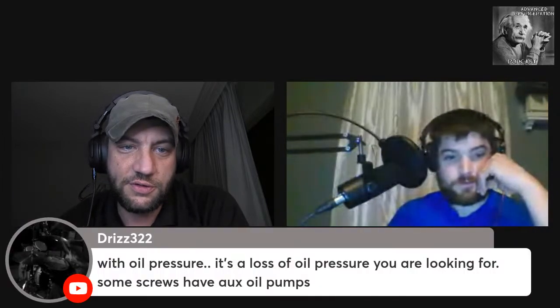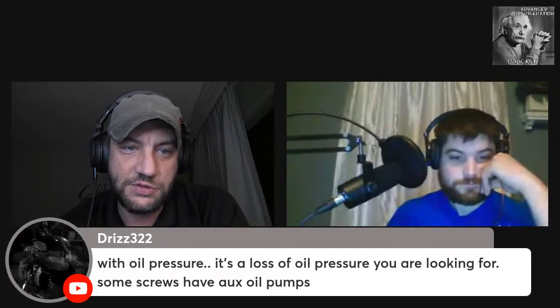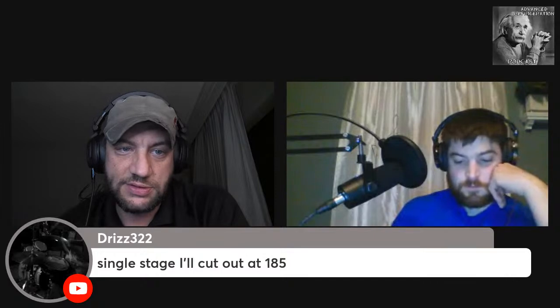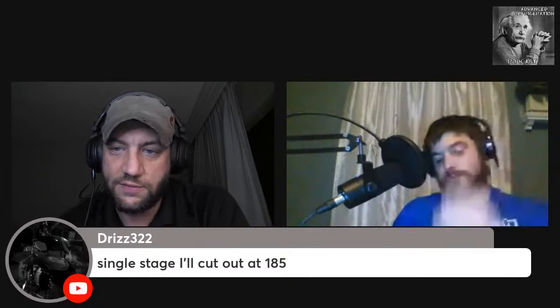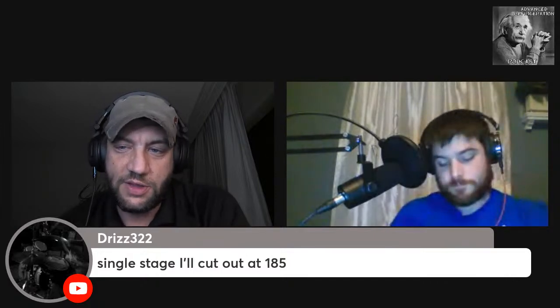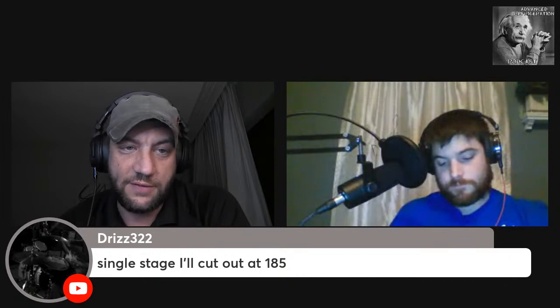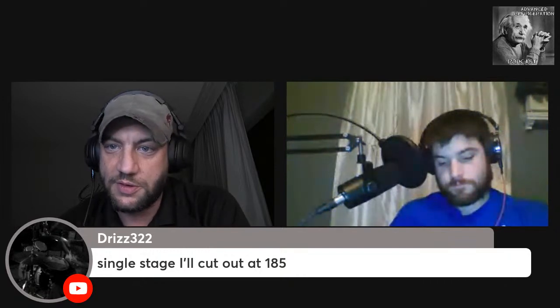Dre, with oil pressure, the loss of oil pressure you're looking for, some screws have auxiliary pumps. So Andre works on industrial, Frick, Vilter, Sabroe. So that's what he's talking about. And single stage, they'll cut out at 185. Yeah, but you got to remember, Dre, those are meant to have way lower head pressure. You know what I mean?